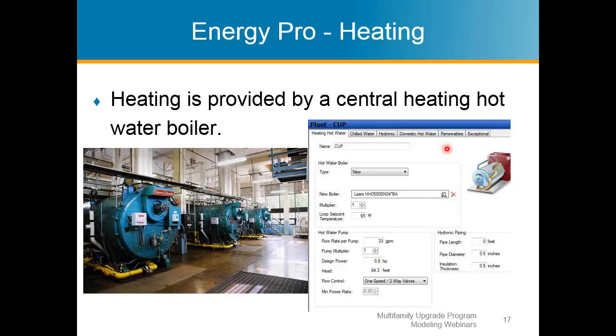Now, it's going to have the same situation where you have pumps and you have head to overcome, and you make sure the water gets to where it needs to get to, and your set point loop temperatures, things like that. But just keep in mind, this is when you're actually going to be using the heating hot water tab. I would imagine in most scenarios, we're all using the domestic hot water tab when we're doing EnergyPro modeling. But when we're dealing with central plants, you're going to be using the heating hot water tab. So hot water used to heat your space, as opposed to hot water used for domestic use of showering, washing hands, and things of that nature.